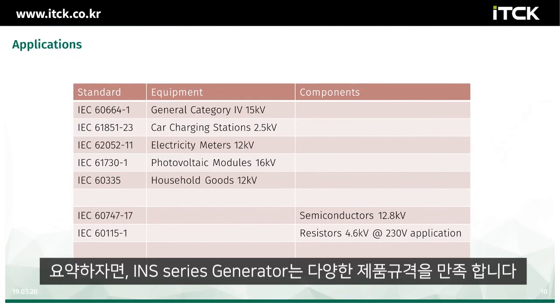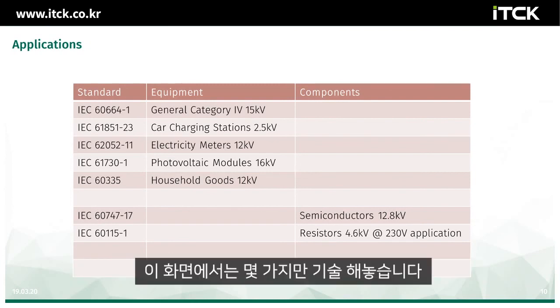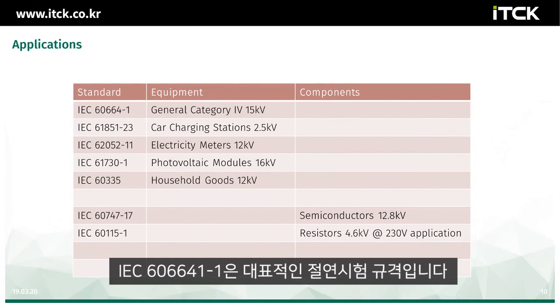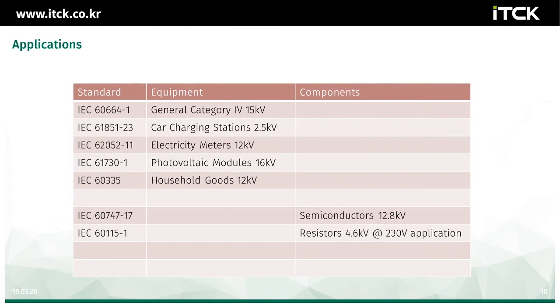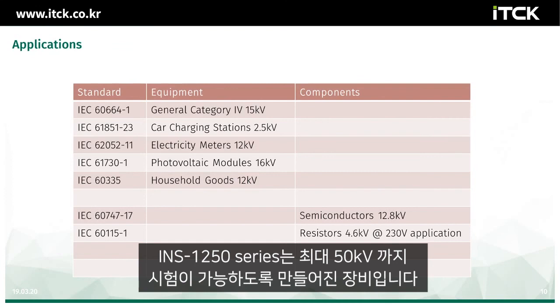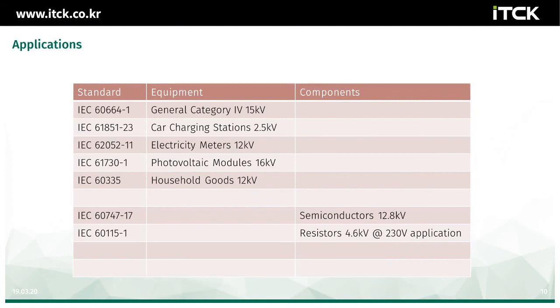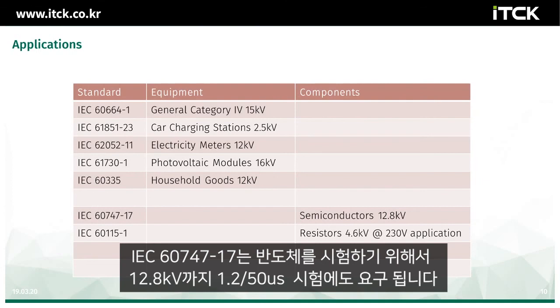As a recap, the INS series generators fulfill many product standards. Below and on this screen we have a small selection. IEC 60664-1 is a general insulation standard, and the INS 1250 series ideally suit this standard for the category 4 testing up to 15 kilovolts. Other standards for testing semiconductors, such as the IEC 60747-17 standard, require the 1.2 by 50 lightning impulse up to 12.8 kilovolt for testing of semiconductor devices.